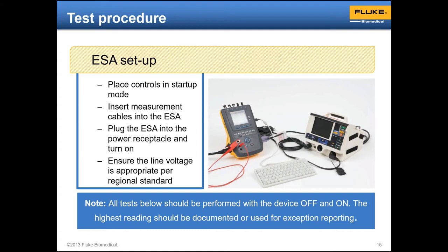And then we're going to do something that I didn't talk about yesterday, but is really important. Before we do any electrical safety testing, we're going to look at the line voltage, that is the voltage coming into our test instrument from the mains power, from the wall panel or a wall connection or ceiling connection, wherever we're getting our mains power.